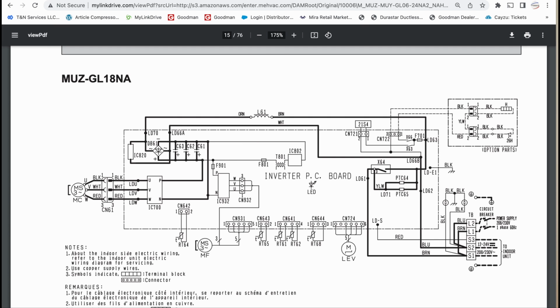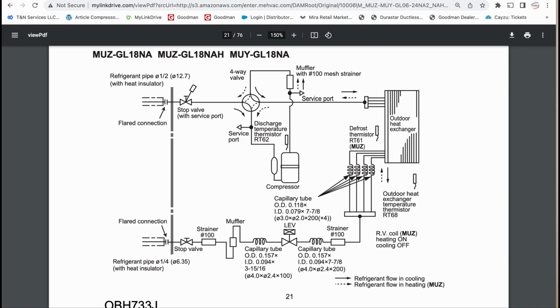Now I'm going to go over to the refrigerant circuit and show you that. It's right here. So you would think that with Mitsubishi, all the units would either energize in heating or all of them would energize in cooling. But we do have some units where the reversing valve energizes in cooling, and we have some where the reversing valve energizes in heating. Well, in this particular case, this GL18, come to the refrigerant circuit, or the refrigerant diagram in the manual, you can actually see right here it says RV coil, heating on, cooling off. That means that this coil energizes in heating, and it does not energize in cooling.